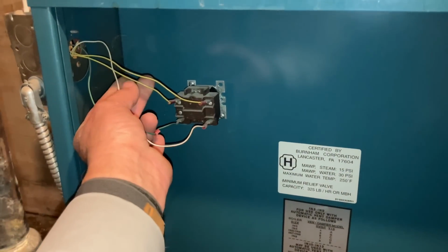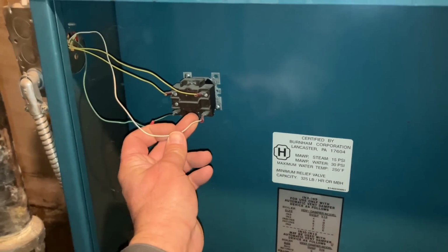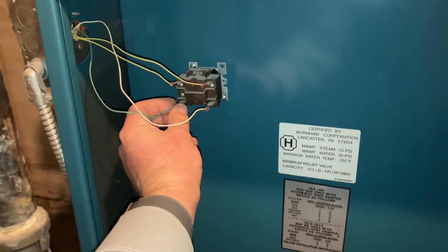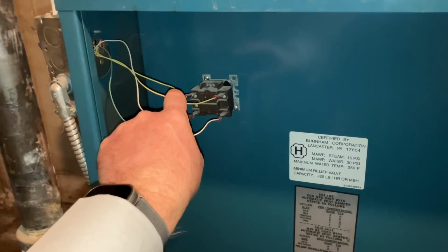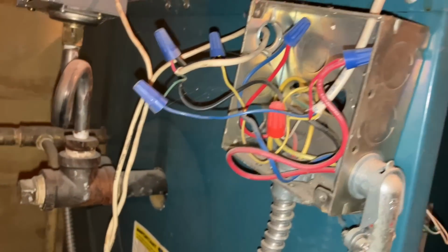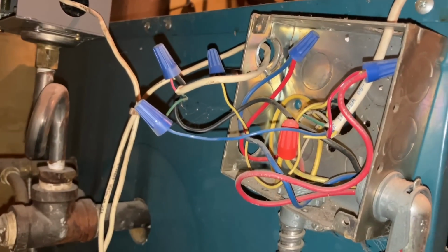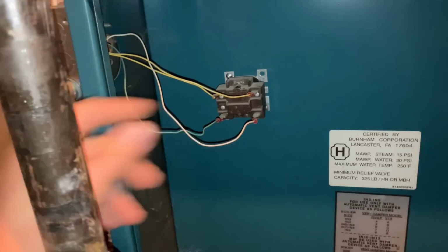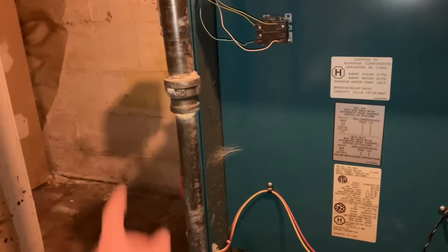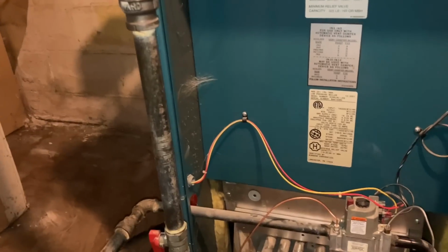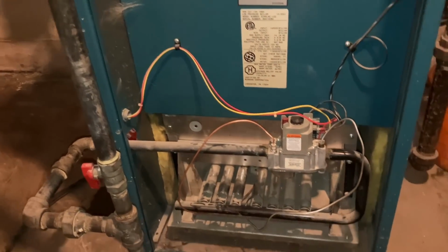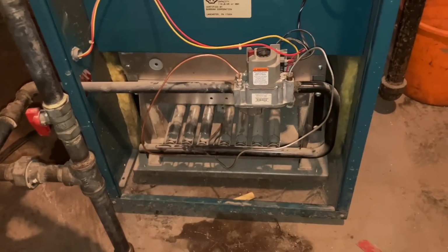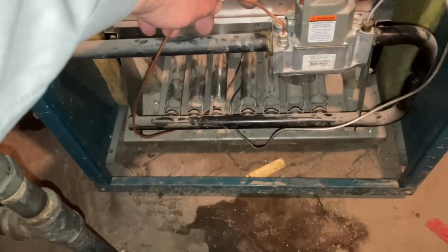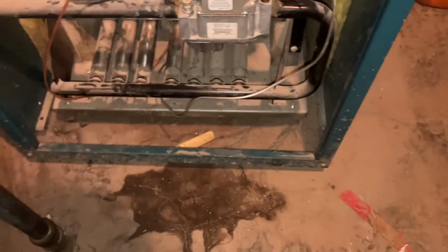This thing with the 2 yellows and the white and the green thermostat wire was not factory, but this is called the thermostat relay. When there's a call for heat, oh my God, the menagerie of wiring here. When there's a call for heat, this clicks and it sends voltage to our low voltage circuit for the safety circuit, which powers the gas valve once everything else is closed. Here's the gas valve, standing pilot. There's the thermocouple. Here's the pilot tubing.